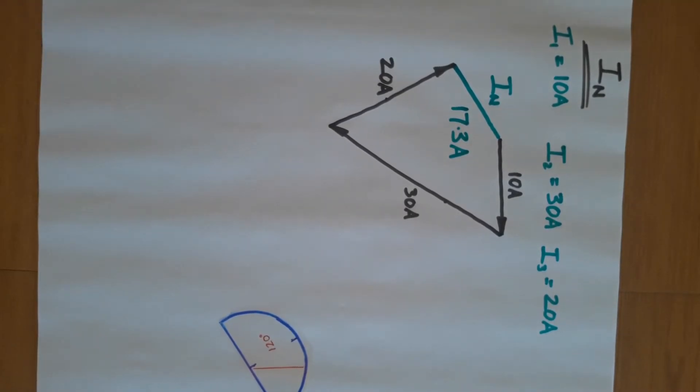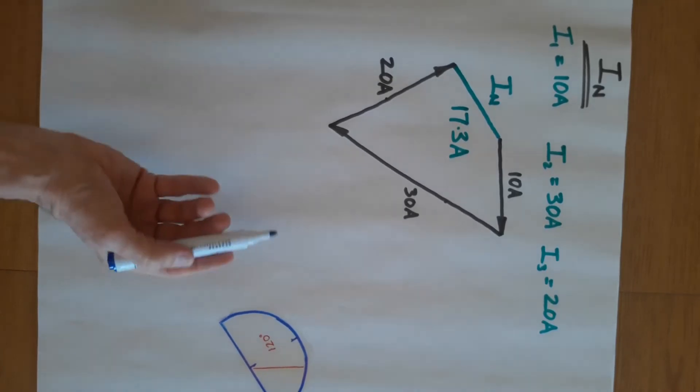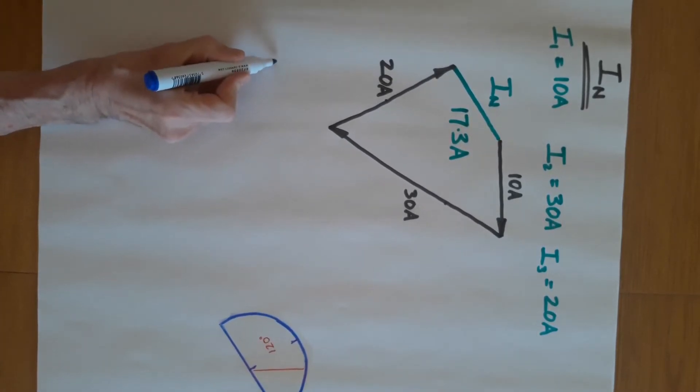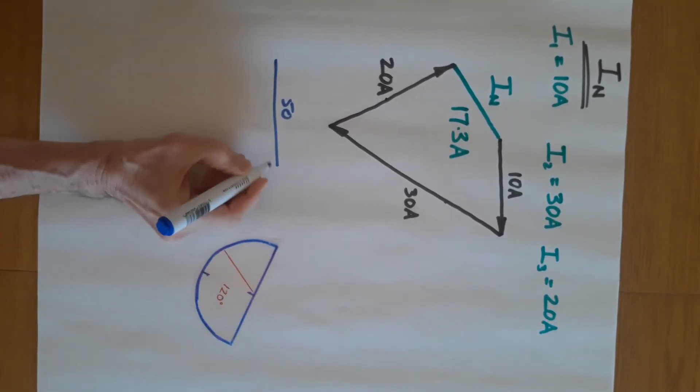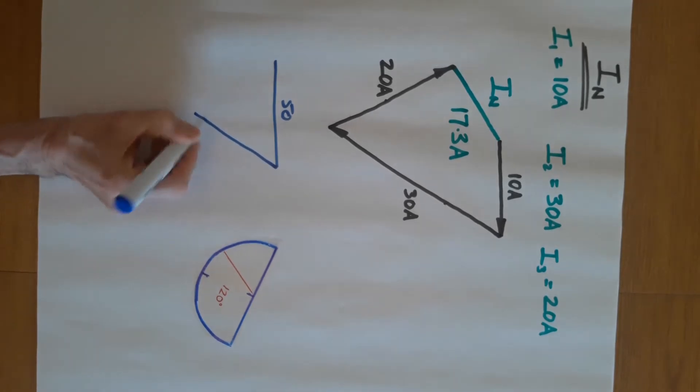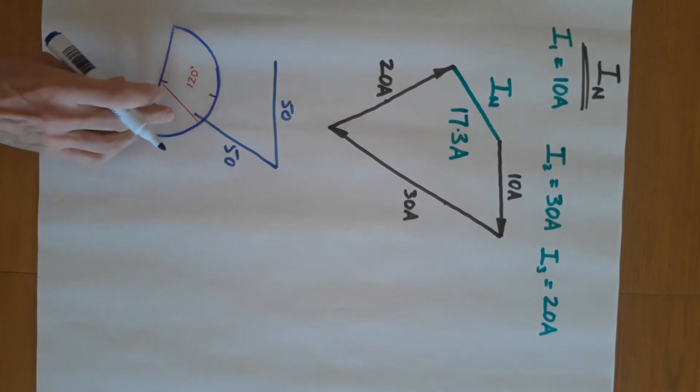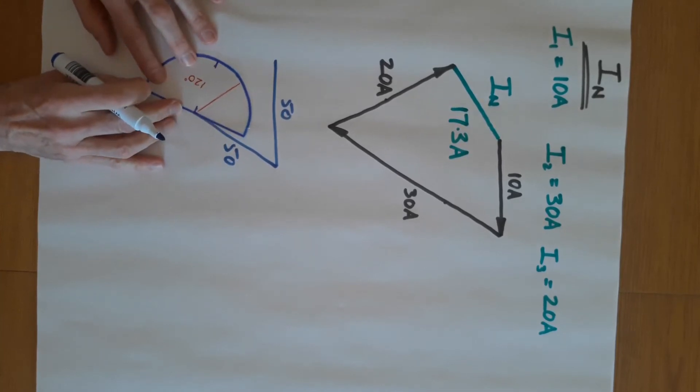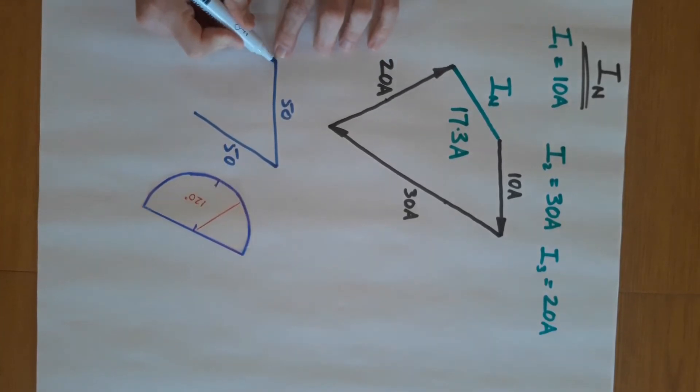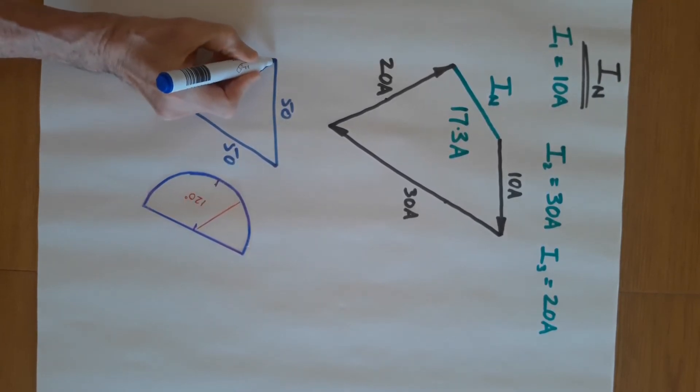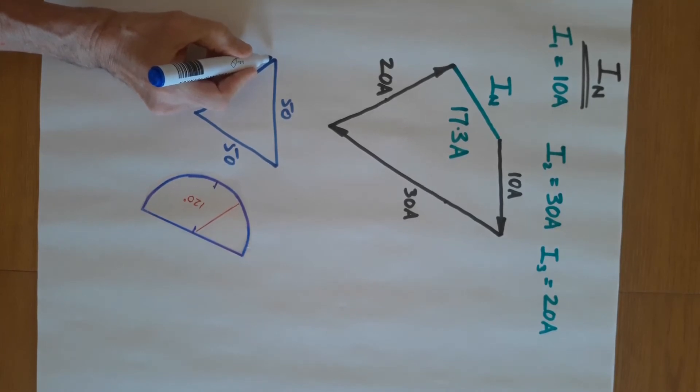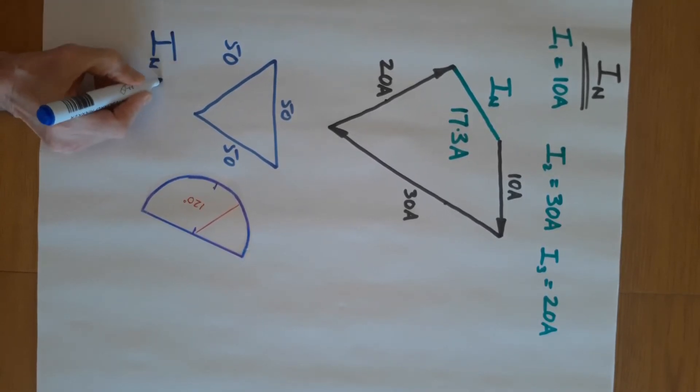Okay, so just a quick consideration of some different scenarios. If we had three equal currents in a system, suppose each current was 50 amps. Then you're going to draw a line that is 50, come around 120 degrees, draw another line that is 50, come around 120 degrees, draw another line that is 50. And you'll find that if they're all equal, then where you start is where you finish - in other words, there is no neutral current.